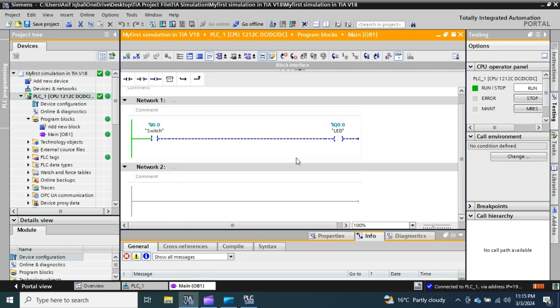This was a very basic demonstration, but the most important thing I observed during this video is that the CPU you want to simulate must have firmware version 4 or above. Not version 2.2 or 3 — if the firmware version is below 4, the simulation will not work. Keep this in mind: for simulation, always select a CPU with firmware version 4 or above.